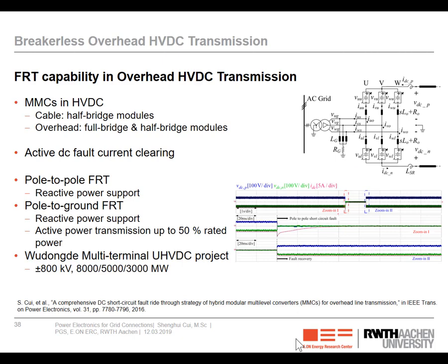And here is the breakerless operation scheme in an overhead HVDC transmission line. We know that for overhead transmission, a short circuit fault normally occurs because of either lightning or air pollution. So for an overhead transmission line, we also need a certain scheme to manage the fault. But you can imagine that a DC circuit breaker is already very difficult in medium voltage application. So high voltage application, of course, is more difficult. So it's better to also have a breakerless operation scheme for HVDC transmission.